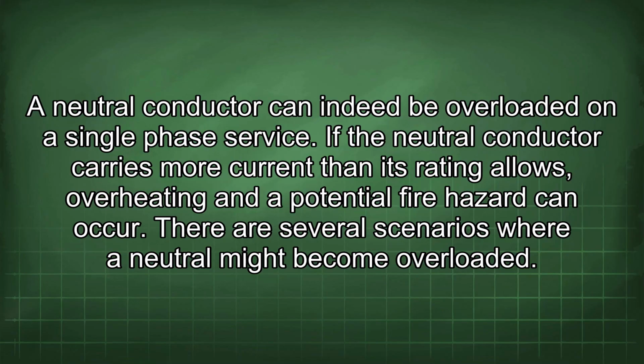A neutral conductor can indeed be overloaded on a single-phase service. If the neutral conductor carries more current than its rating allows, overheating and a potential fire hazard can occur. There are several scenarios where a neutral might become overloaded.